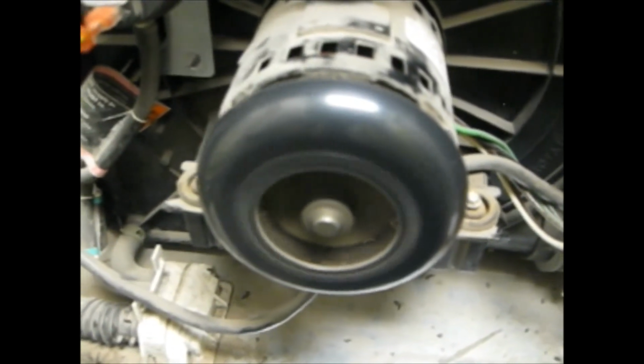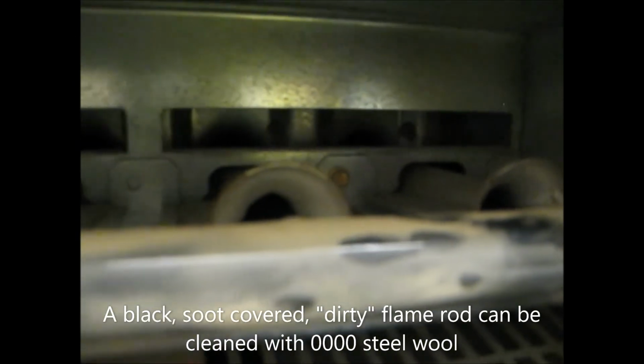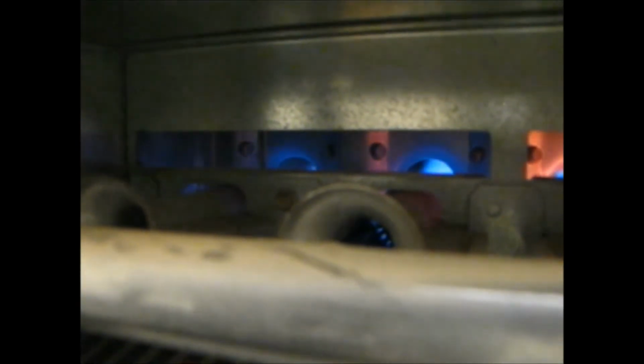Okay, the inducer motor is turning. Soon our pressure switch is going to close, and we're going to get the hot surface igniter running, and then the gas valve is going to open to let things flow. Now, we will get a flame, but because I disconnected the flame rod, that flame will soon go out after it ignites. Okay, there's our igniter getting cherry red. The valve is open, the gas is flowing, and it's out because the flame rod is disconnected.